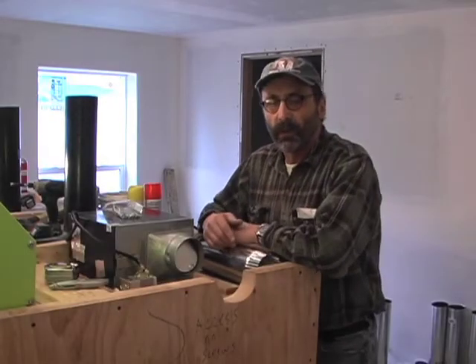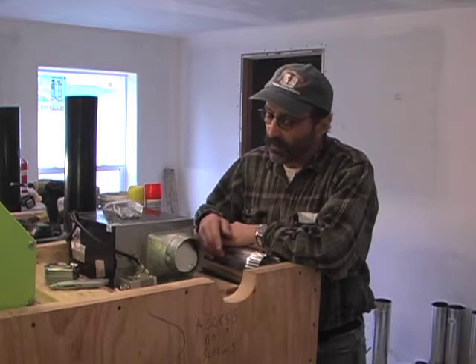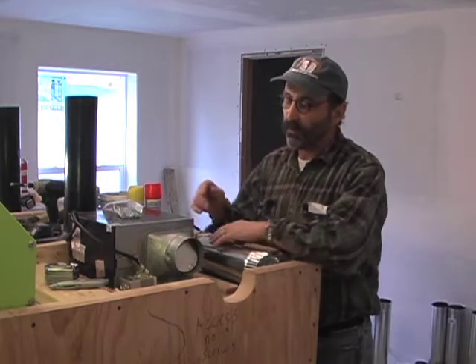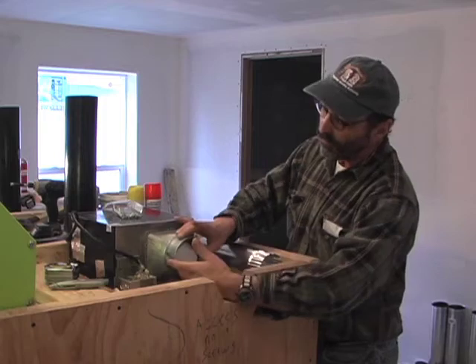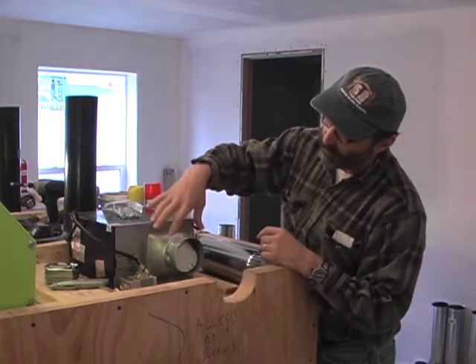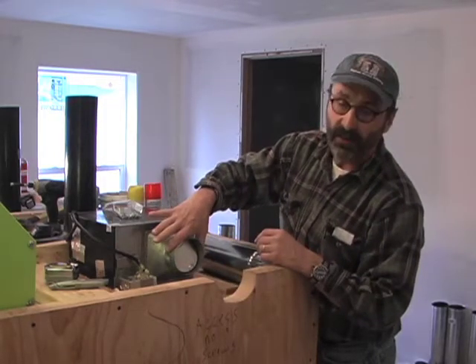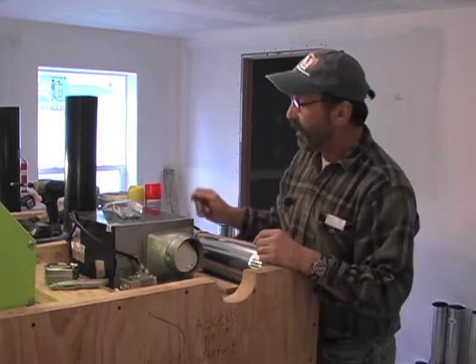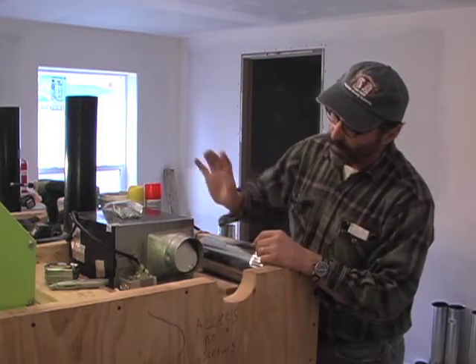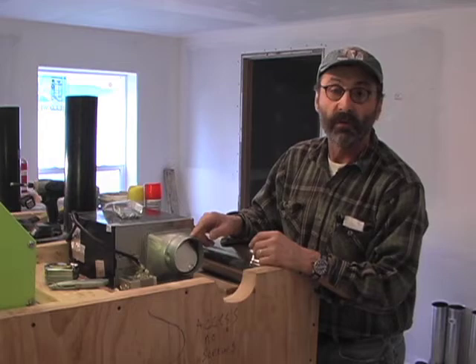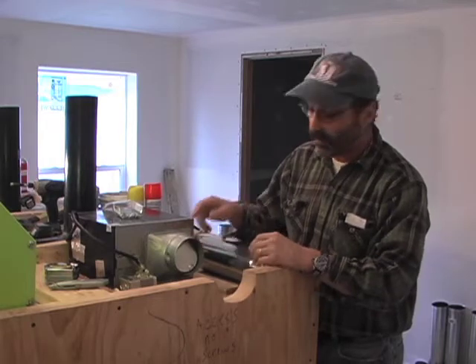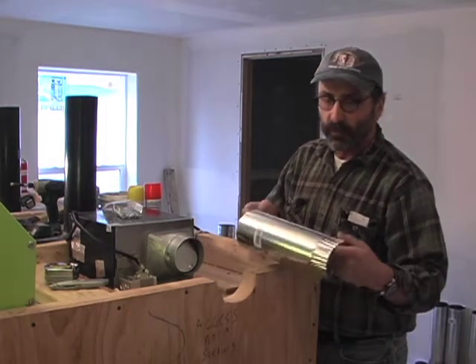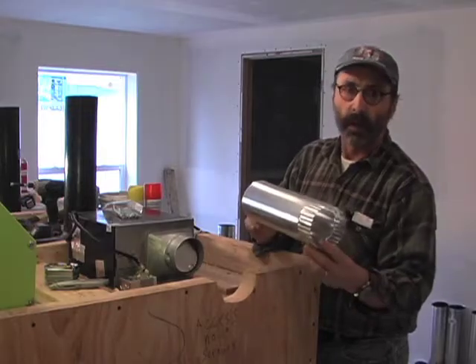Ducting, it doesn't matter whether it's for a ventilation system or an exhaust device like this bathroom fan. As we start our ductwork on here, we want to make sure that this is sealed with either a latex-based mastic or a metal foil tape. This is one area where, just like with dryer ducting, you don't want to put fasteners into this type of ducting. My preference would be to keep the seams up, not on the bottom.